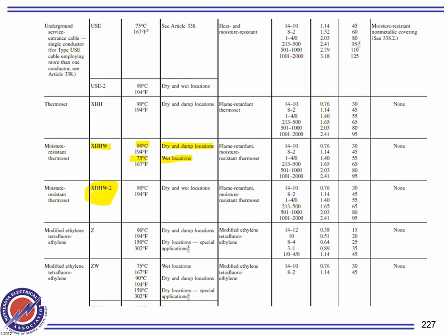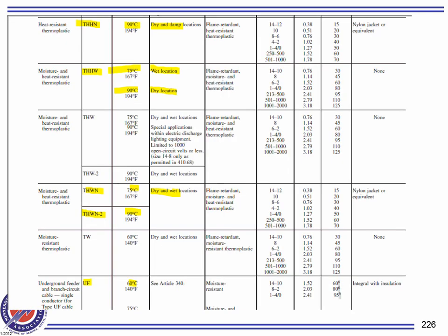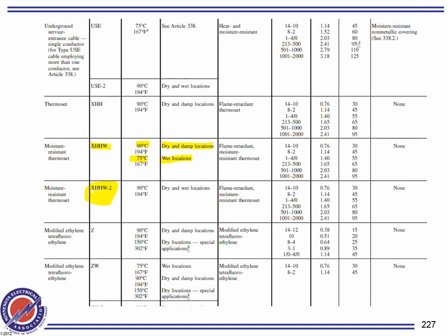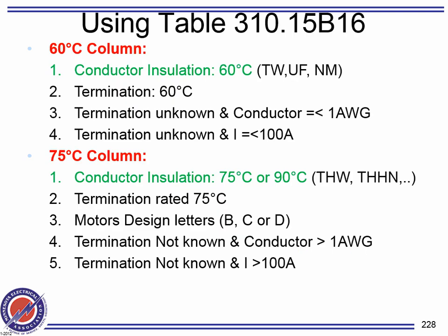Okay, so the first thing you need to know is wet or dry. Now let's go to the rules. Everybody's good? Let's go to the rules. 60-degree column. I'm going to be jumping. Go to 3. Make sure you are at 310.15(B)(16), because that's what we're going to be talking about.